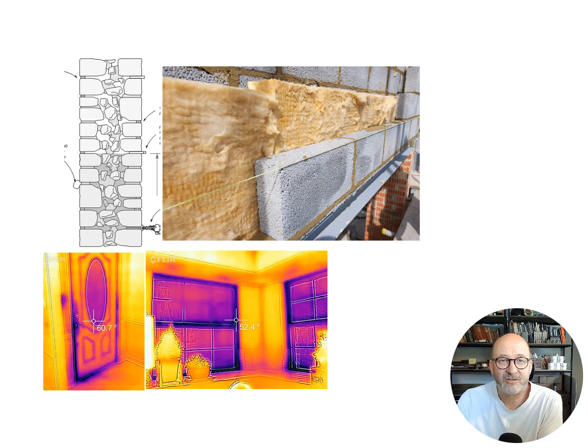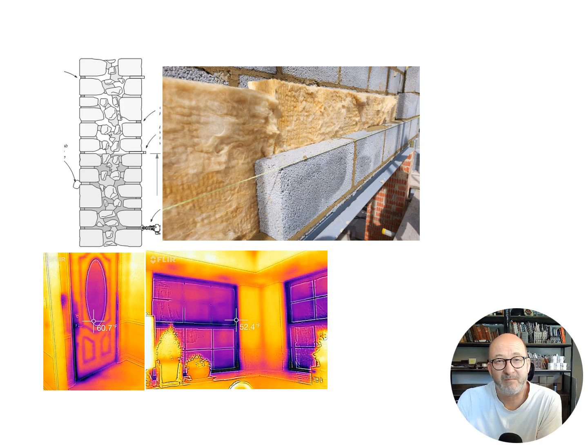Secondly, dew point calculation models are based exclusively on moisture diffusion theory — moisture molecules moving through building materials. The problem is that in reality, air leaks in and out of walls and cavities rather than moisture diffusion, and this accounts for a large proportion of moisture transmission in buildings. Because of variations in workmanship, construction details, the use of sealants and similar variables, the relative contributions of diffusion and air leakage in walls and ceilings is very unpredictable.